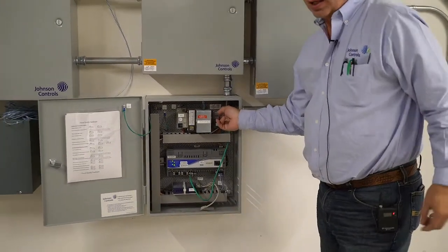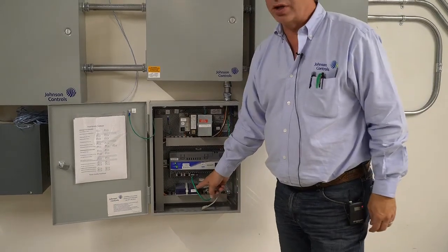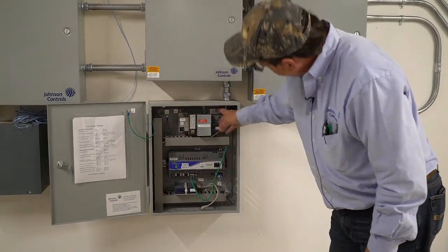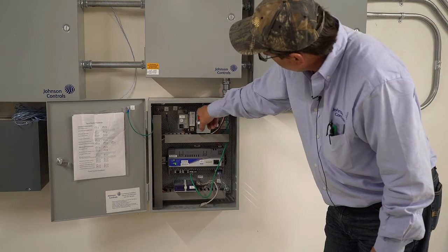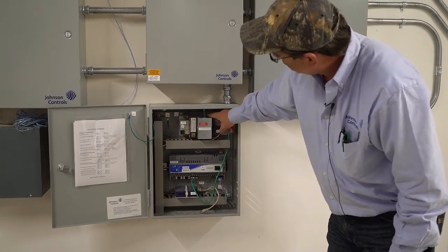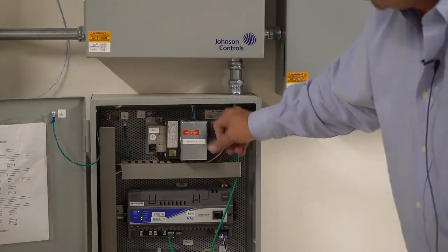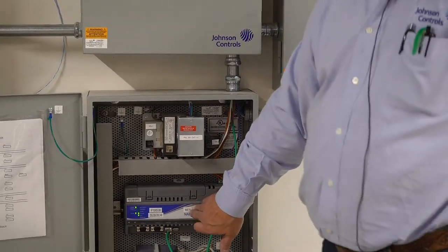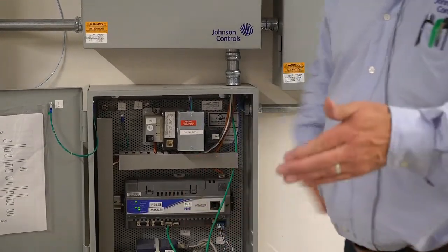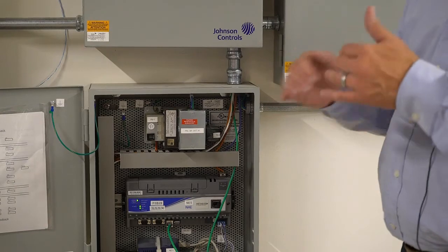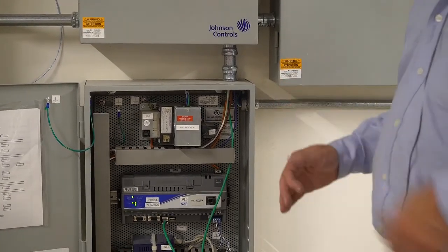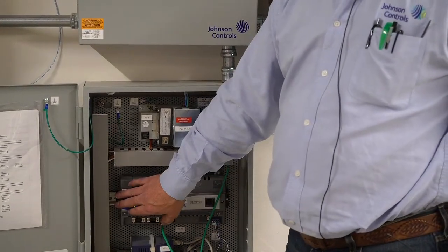The power supply that's plugged in here feeds the switch down here. There is a rocker switch up here behind this power. I don't know if you can see this little red rocker switch back here. But if you shut that off, that'll kill the power to the controller. The controller won't shut off right away. It'll go through a controlled shutdown, and then after like a minute or so, it'll shut down and the lights will shut off.